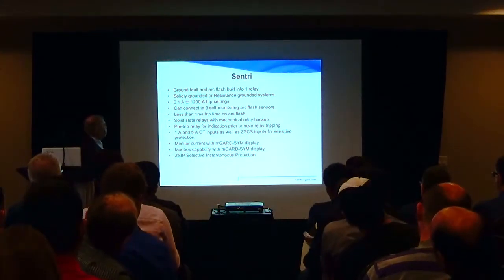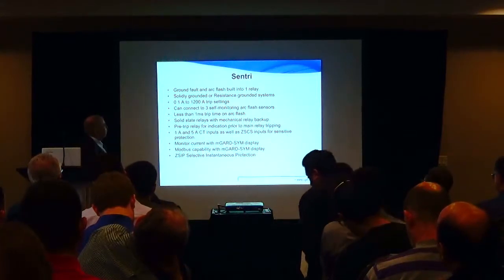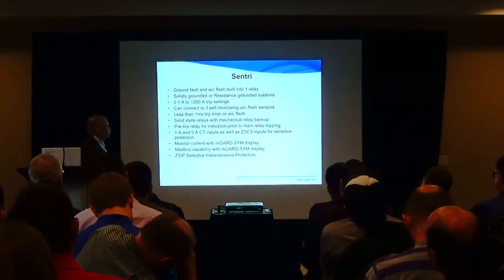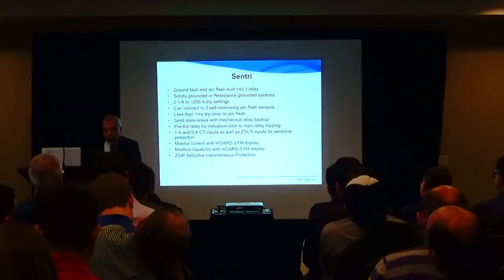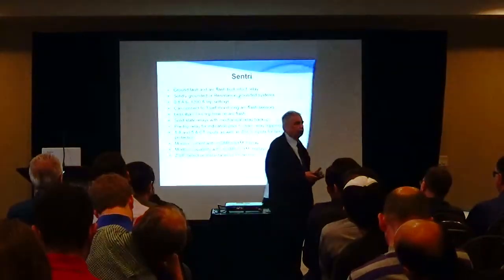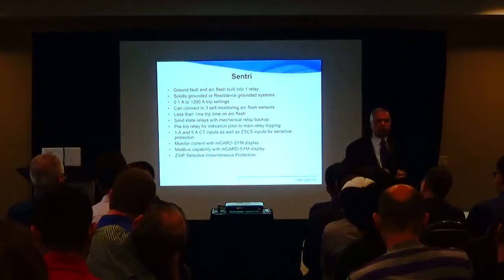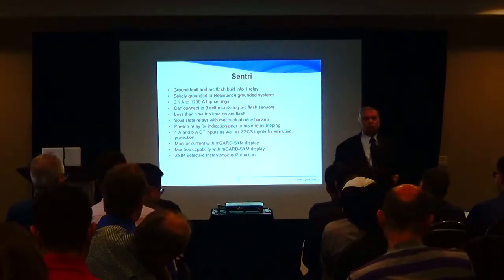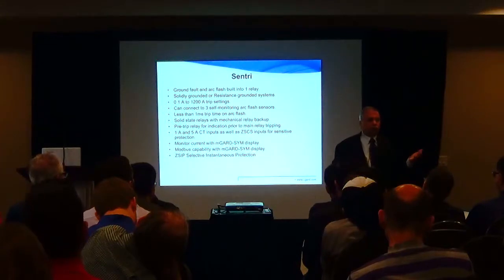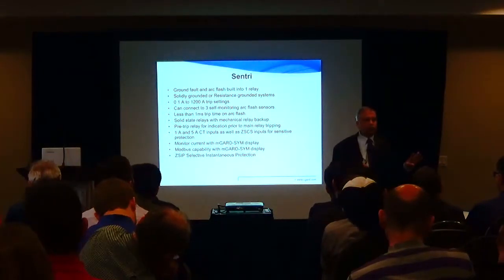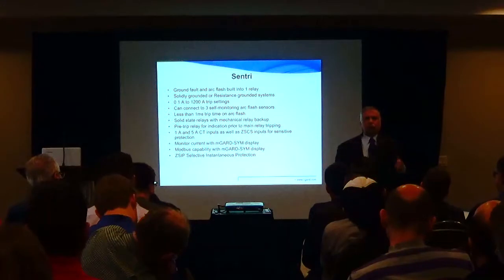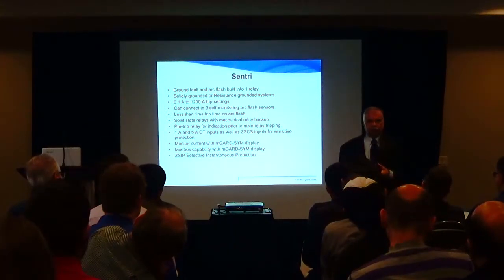It has three arc flash sensors. The tripping time on the arc flash is 1 millisecond, so a very rapid effect, and then the breaker trip time gets added to it. If you step back and see what the breaker situation is these days, we are using molded case breakers for low voltage distribution, 480 and 600 volts. These molded case breakers are roughly 2.5 cycles of operating time. We have insulated case breakers from all suppliers, with similar operating time. For medium voltage, we have vacuum breakers. The old SF6 is obsolete, so now only three types of breakers are there: vacuum breakers, insulated case breakers, and molded case breakers. All these breakers are 50 milliseconds operating time or less.